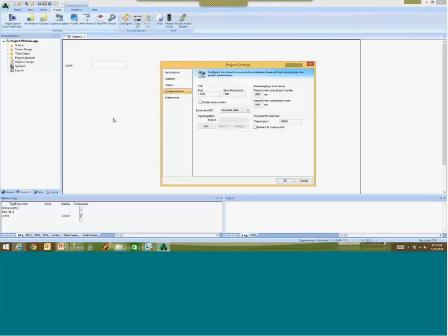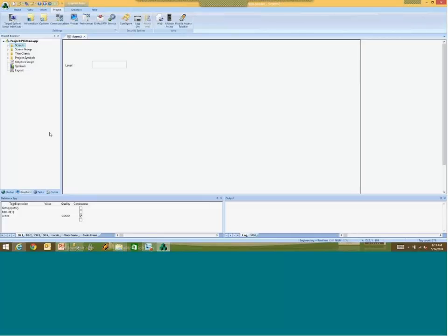So you write 1 to the tag on the on down and write 0 to the tag on the on up. If you select Send Last State, it's possible that you can click the button so fast that by the time the driver receives the information, you have already executed the on down and the on up. So the send last state will only send the value 0 to the PLC. It will not send the value 1 as well.